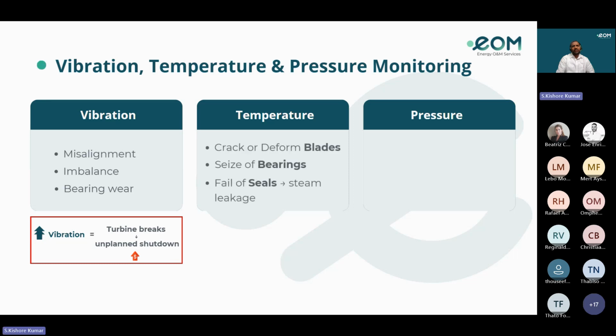Temperature monitoring. So we check the temperature of important parts of the steam turbines, like metal temperatures of blades. The metal can weaken if it gets too hot. Coming to the bearings, it may seize because of the high temperature. If it's too hot, it will lose the friction and lead to damage of the bearings. And coming to the seals, they may fail because of overheating, which also causes leakages.